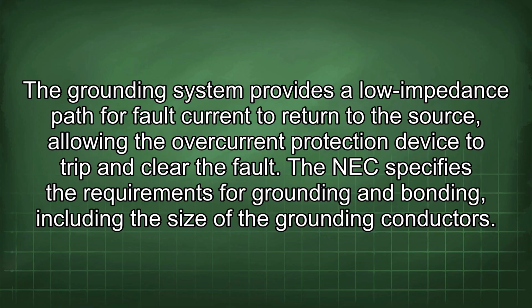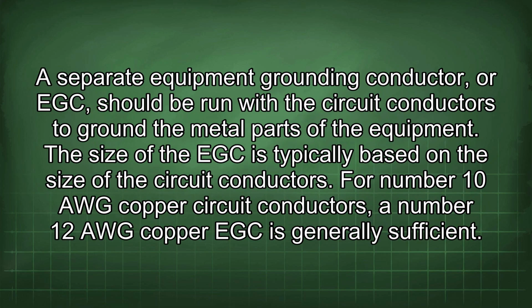The NEC specifies the requirements for grounding and bonding, including the size of the grounding conductors. A separate equipment grounding conductor, or EGC, should be run with the circuit conductors to ground the metal parts of the equipment. The size of the EGC is typically based on the size of the circuit conductors. For number 10 AWG copper circuit conductors, a number 12 AWG copper EGC is generally sufficient.